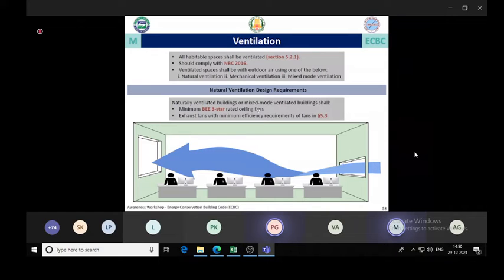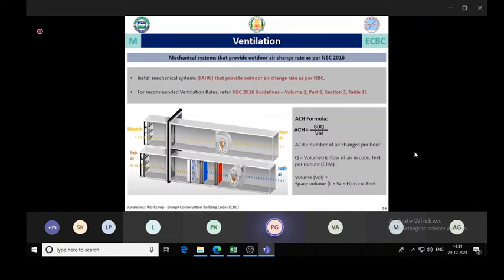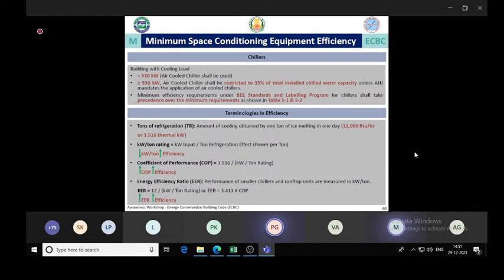And in such spaces, if there are ceiling fans, they should be BEE 3-star rated ceiling fans. And if there are exhaust fans in these areas, they also have some minimum efficiency requirement, like the efficiency should be minimum 60% or above. Right. Now, from the equipment efficiency point of view, there is one interesting mandatory requirement specified here, which says that when the total load of the building is less than 530 kilowatt, so that is roughly 150 tons, then air-cooled chillers can be used. If it is more than 150 tons, in that case, air-cooled chiller capacity is restricted to 33% of the total installed tonnage. So the objective here again is, as you know, water-cooled chillers will have better efficiency. So if it is more than 150 tons, they encourage us to use water-cooled chillers rather than air-cooled chillers.